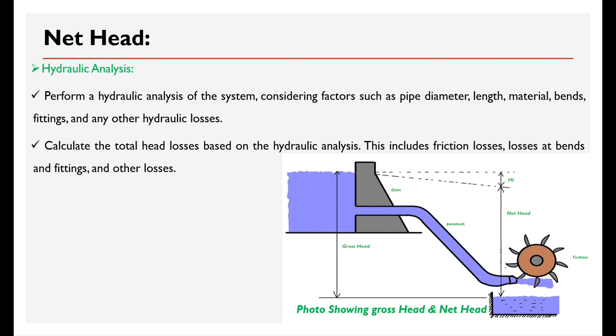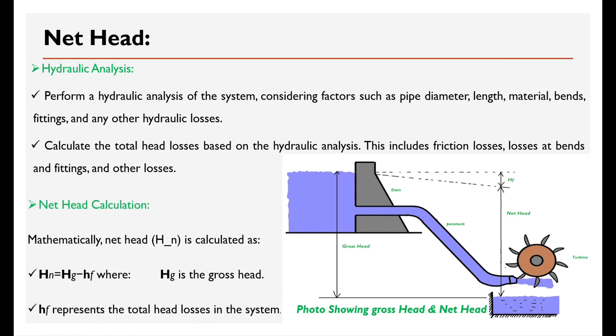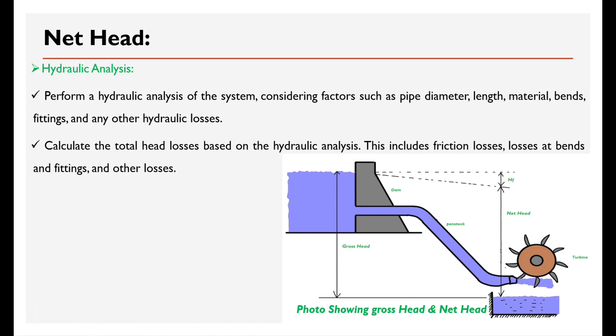Hydraulic analysis: Net head is calculated based on the hydraulic analysis of the system, considering factors such as pipe diameter, length, material, bends, fittings, and any other hydraulic losses. Calculate the total head losses based on the hydraulic analysis. This includes friction losses, losses at bends and fittings, and other losses.